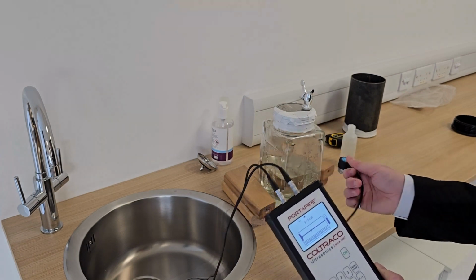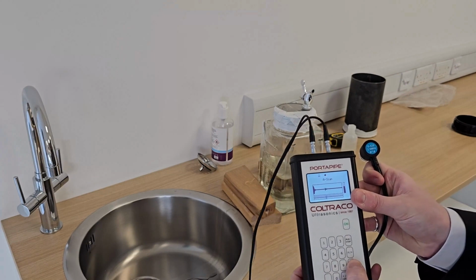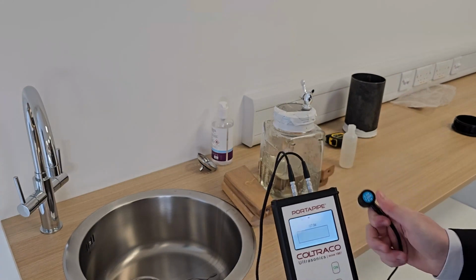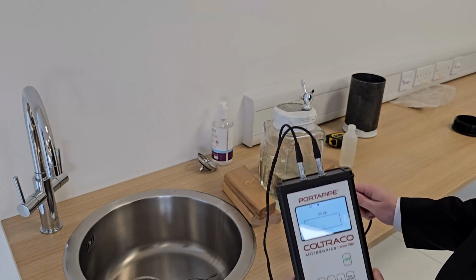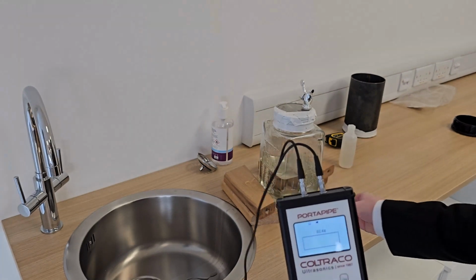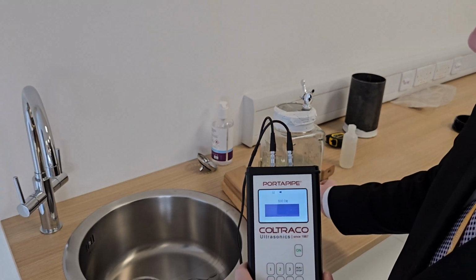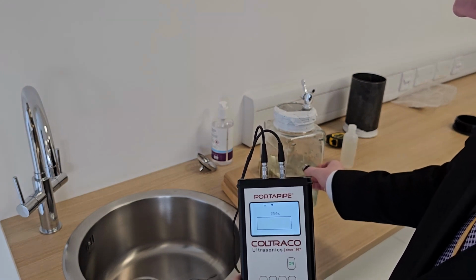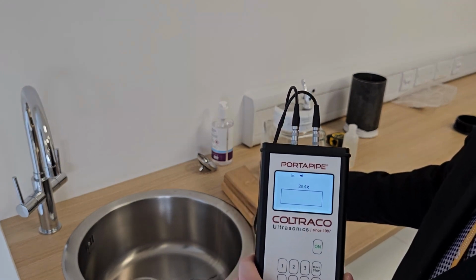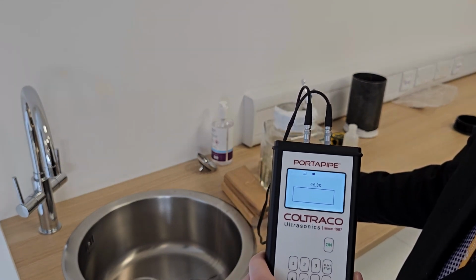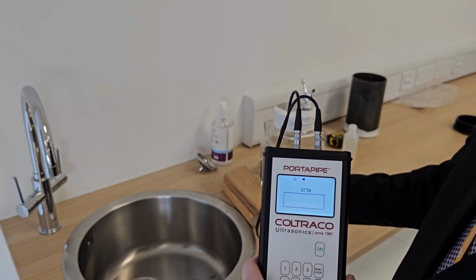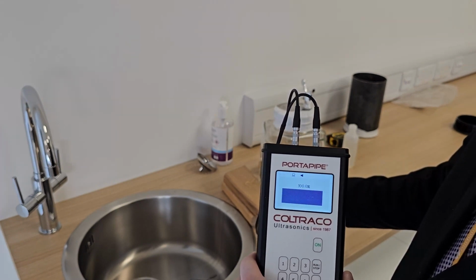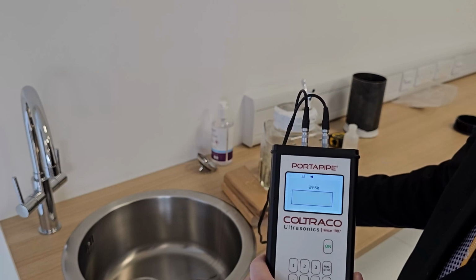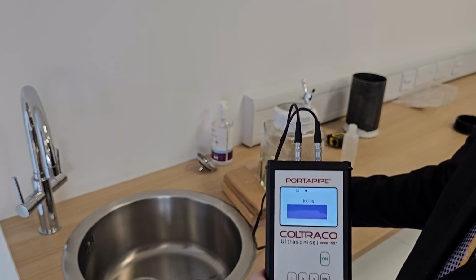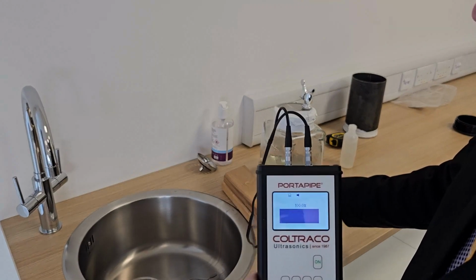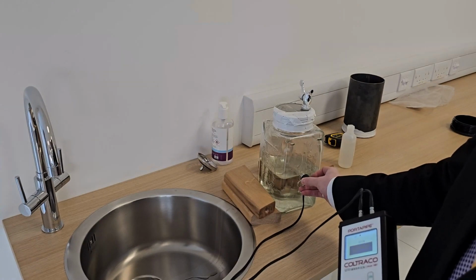To make things easier, you could go back to the percentage fill screen. This time we're not looking for a specific number, just 100% when we're below the level - above it, the value bounces around randomly and won't fix onto anything. So as I move down, there's a point where the device locks onto 100%, and that's the moment the sensor has just entered the liquid.